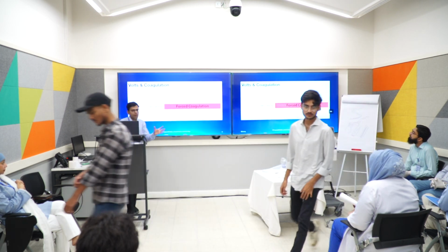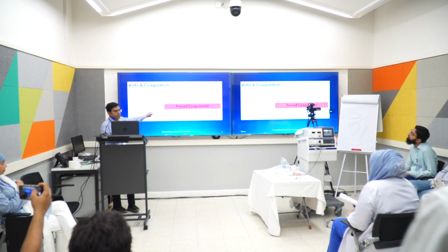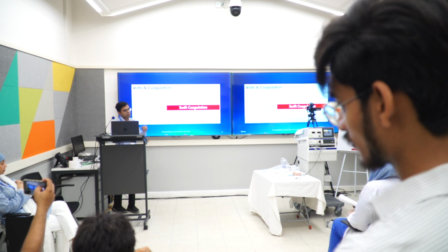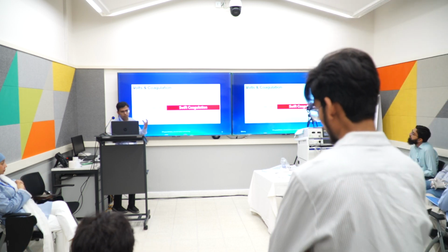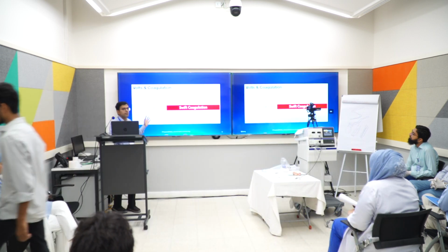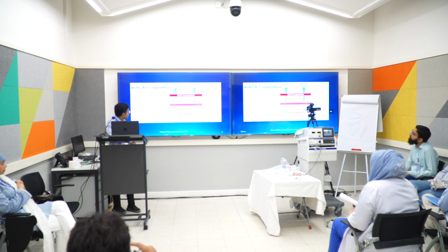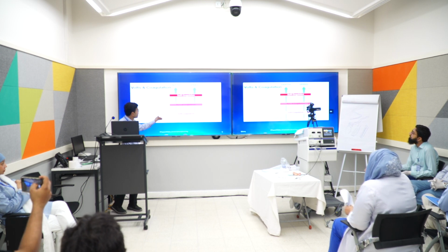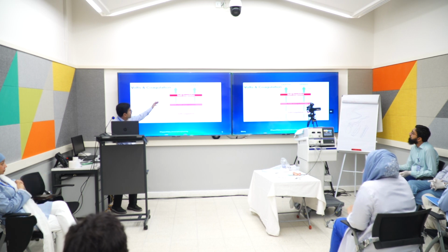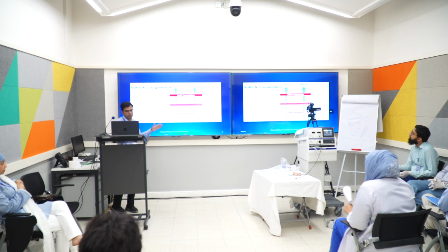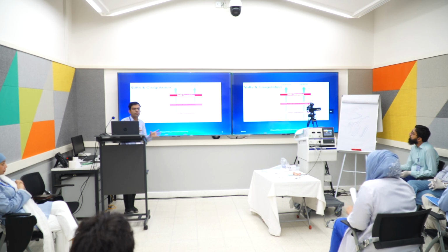Second is forced coagulation. You can see the voltage is much higher, around 1800. Third is swift coagulation. This is the fastest and has got more depth. The voltage is around 2500. So if we compare all three, we can easily appreciate that for superficial vessels and superficial tissues, soft coagulation will help. As we move further till swift coagulation, the depth increases and the rapidity of the current also increases. So this is how voltage defines coagulation in diathermy.